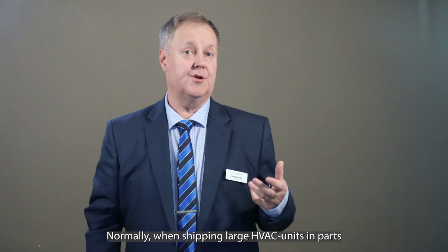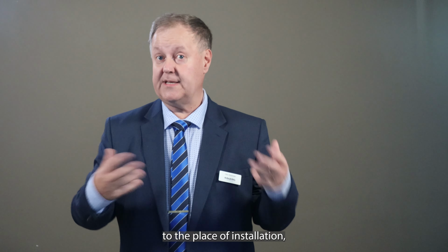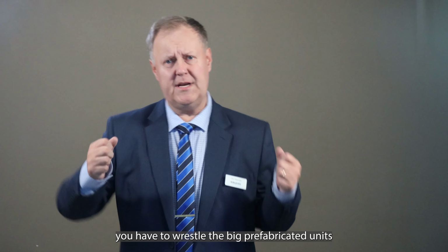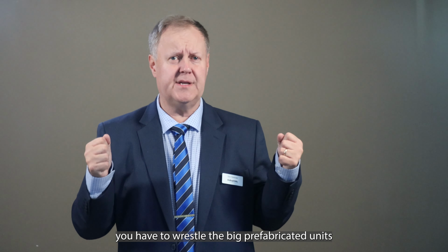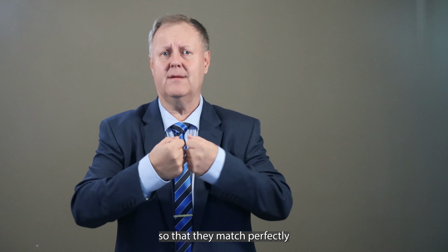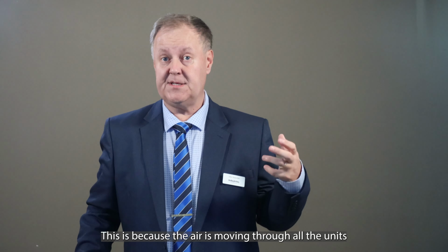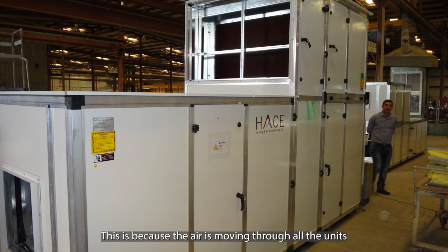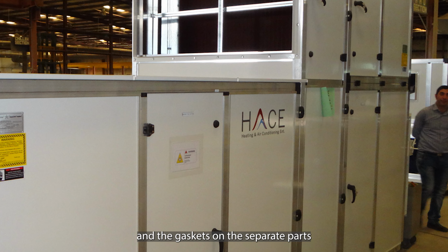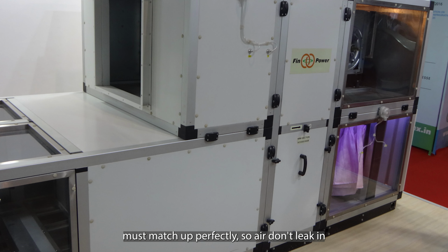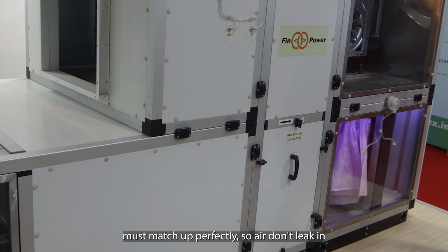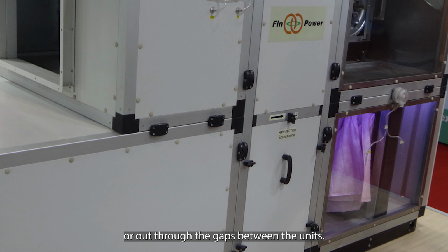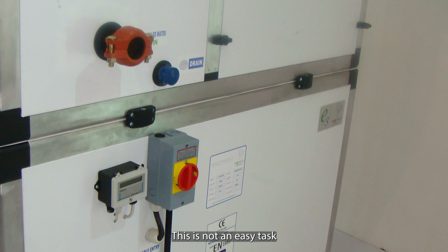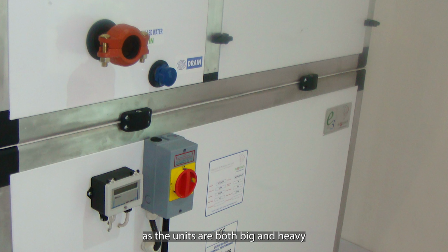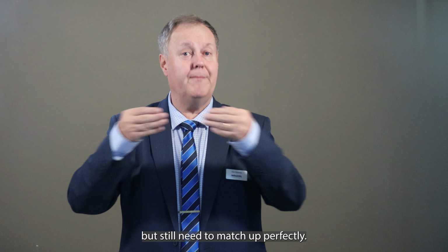Normally, when shipping large HVAC units in parts to the place of installation, you have to wrestle the big prefabricated units so that they match perfectly when reassembling it. This is because the air is moving through all the units and the gaskets on the separate parts must match up perfectly so air doesn't leak in or out through the gaps between the units. This is not an easy task as the units are both big and heavy but still need to match up perfectly.